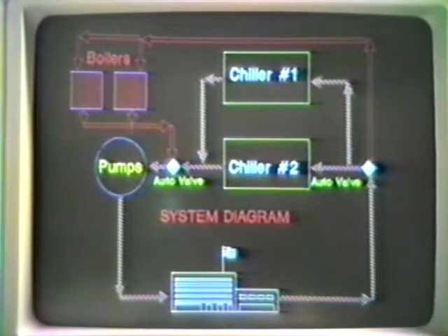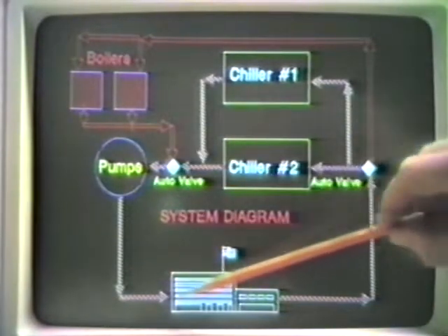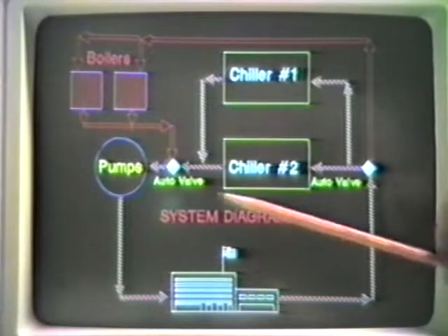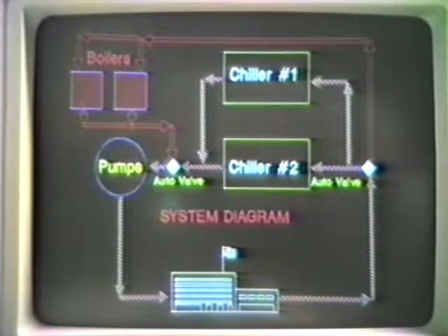Let's look at our chilled water operating system. We have used two Trane 100-ton air-cooled chillers. These are package machines using semi-hermetic reciprocating compressors. Each chiller is designed to cool 211 GPM of water-antifreeze mixture to 45 degrees on its way, pumping it into the fan coil units in the buildings. The chillers operate automatically when enabled to run from the system control panel, which coordinates the overall system functions. Later, we'll discuss this control panel in more detail.